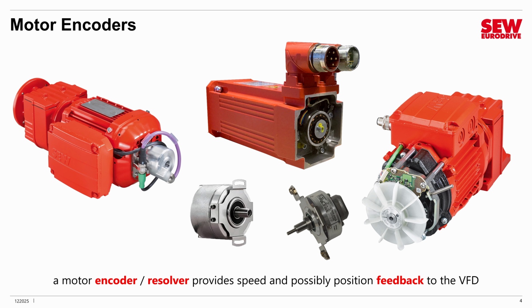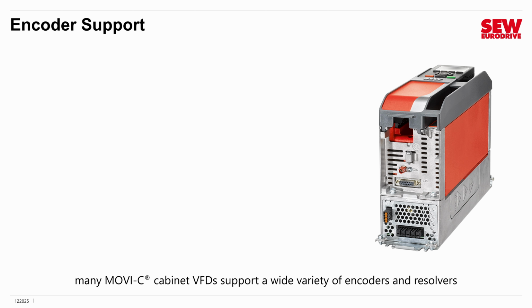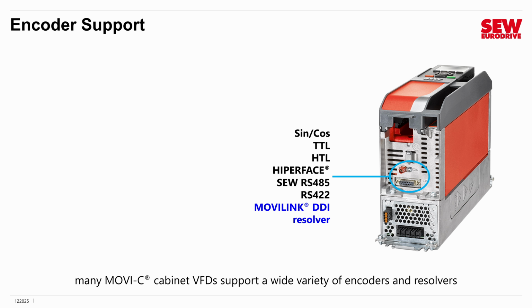There are many different types of motor encoders, but if you've got one, it's very likely you'll be able to connect it up to a MOVI-C VFD and take advantage of its feedback. Many MOVI-C cabinet VFDs have what's called a multi-type encoder interface, meaning they can work with a wide variety of encoders and resolvers. The MOVI-Drive technology is certainly in this category, and it supports, as you can see, many common encoder and resolver standards like sine, cosine, TTL, HTL, hyperface, SEW RS485, which is sort of like hyperface, RS422, MOVI-Link DDI, and resolvers.